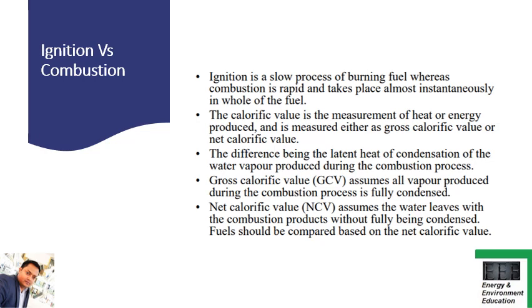Calorific value is a measurement of heat or energy produced, measured as either Gross Calorific Value (GCV) or Net Calorific Value (NCV). The GCV assumes all vapor produced during combustion is fully condensed, while the NCV assumes water leaves with the combustion products without being fully condensed. The difference between the two is essentially the latent heat of condensation of the vapor. Importantly, fuels should be compared based on NCV, not GCV.